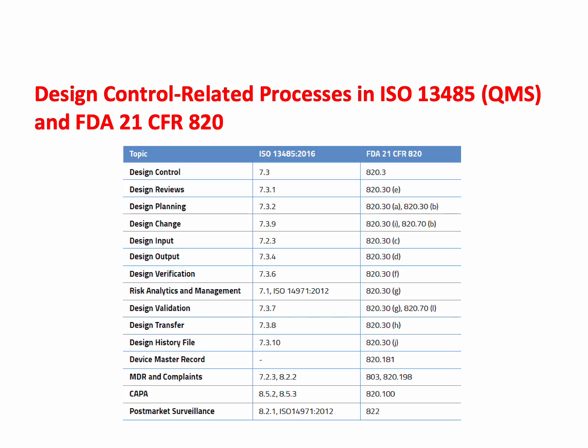Now, you can always refer to ISO 13485 or FDA 21 CFR Part 820 for the quality management system and or quality system regulations. So here, for example, you have on the left side the topics related to the design control, and you do have in the two columns on the right side ISO 13485 and FDA 21 CFR 820.